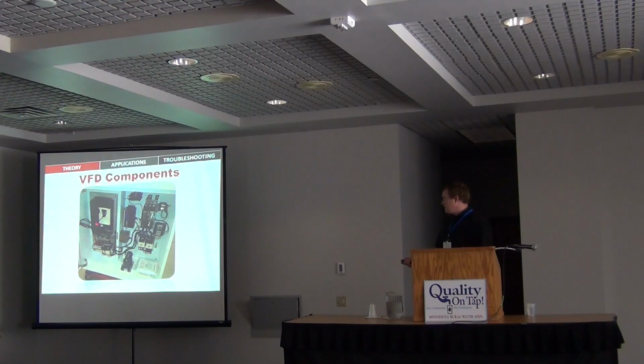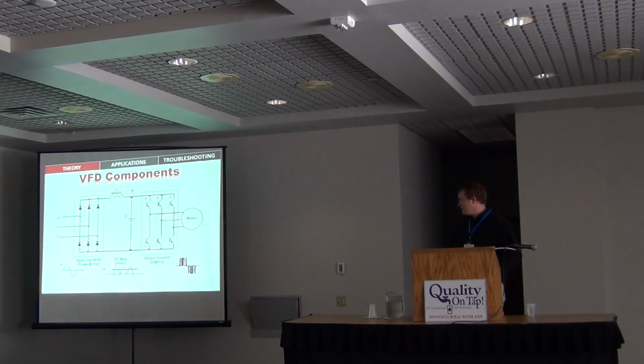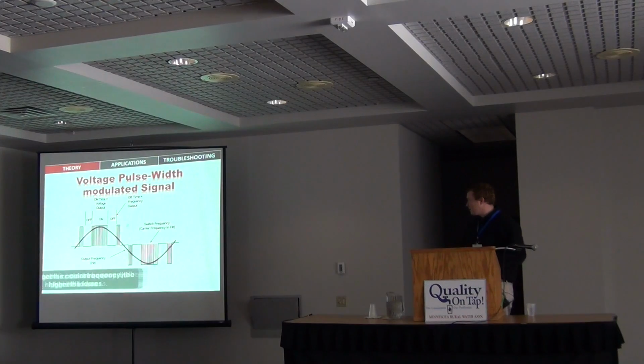So we're going to zoom in, schematically, I guess, into this box, the VFD itself. And this is what it looks like. Power comes in. The VFD itself is going to take that AC three-phase signal and convert it to a DC signal. Once we have it converted to DC, then the device is actually going to output it, modulating it into a three-phase AC signal that can vary the frequency, but it looks kind of weird. And down here, it's kind of showing it, but this next slide, I think, shows it better.